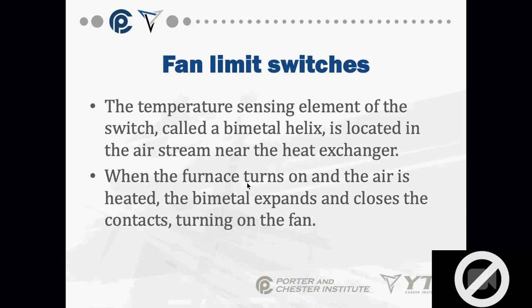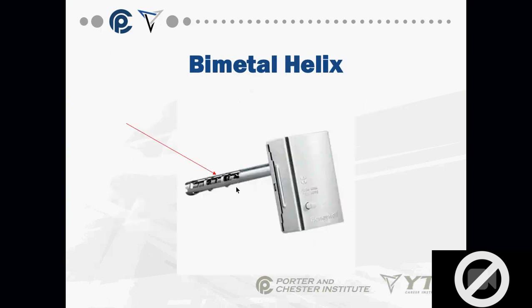The temperature sensing element of the switch, called the bimetal helix, is located in the airstream near the heat exchanger. When the furnace turns on and the air is heated, the bimetal expands and it closes the contacts, turning on the fan. Again, if I have a coil of bimetal or a helix of bimetal, it can actually generate motion. It can generate motion in a circular pattern. The bimetal helix, as I pointed out earlier, is the part that goes into the heat exchanger. Your controls are mounted on the outside of the heat exchanger.